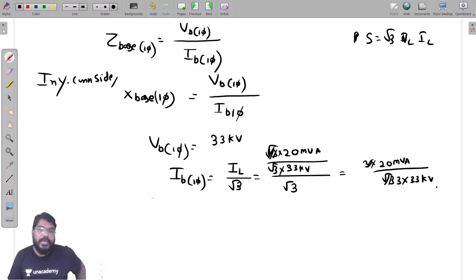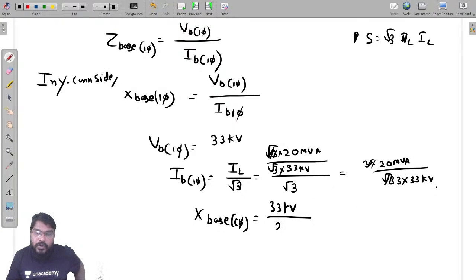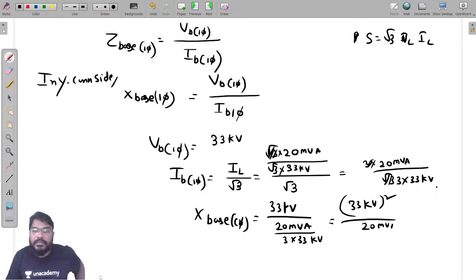This value here is IB base. So now therefore XB base is equal to, in the single phase, it is 33 kV divided by 20 MVA, into MVA divided by 3 into 33 kV. So that is equal to 33 kV whole square by 20 MVA by 3.